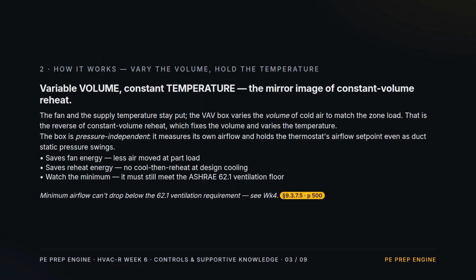How it works. The fan and the supply temperature stay put. The VAV box varies the volume of cold air to match the zone load, the reverse of constant volume reheat, which fixes the volume and varies the temperature. The box is pressure independent. It measures its own airflow and holds the thermostat set point even as duct static pressure swings. That saves fan energy, because you move less air at part load, and it saves reheat energy, because there's no cool-then-reheat at design cooling. The catch? The minimum airflow must still meet the 62.1 ventilation floor. You can't throttle to zero.